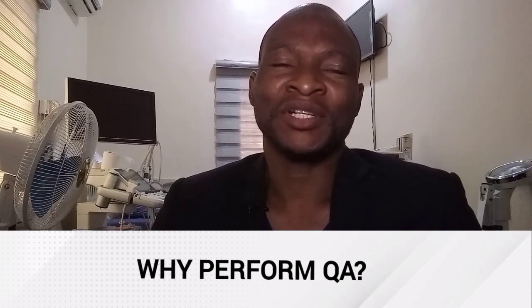Acceptance testing is not performed by the sonologist or the sonographer. It's performed by qualified personnel on new equipment prior to its first use. It quantitatively measures equipment parameters such as power output to ensure that the accepted government or regulatory standards are met, and uses test objects such as a phantom and other sophisticated testing equipment such as hydrophones and force balances.